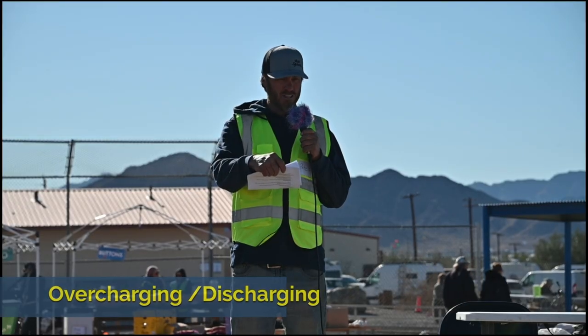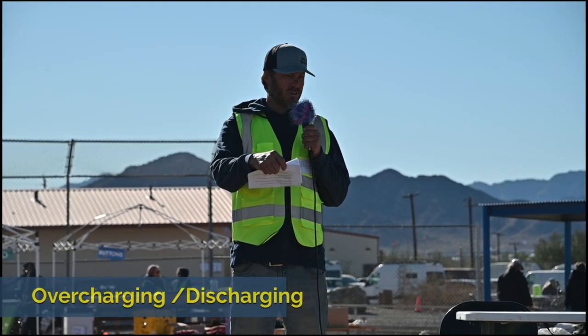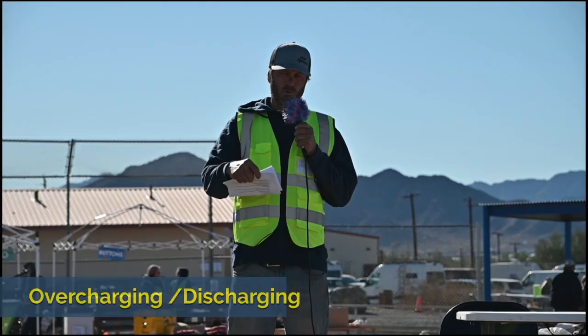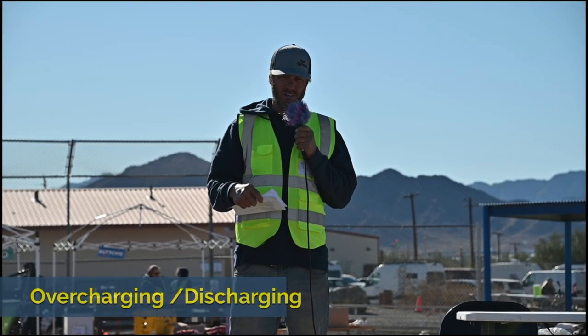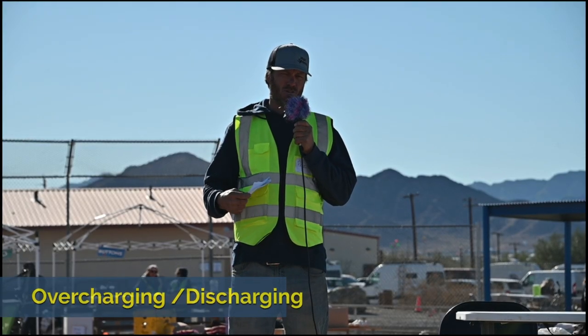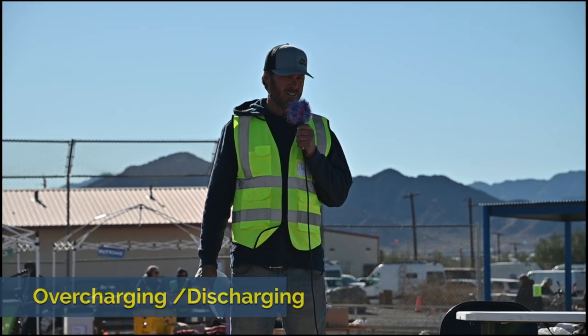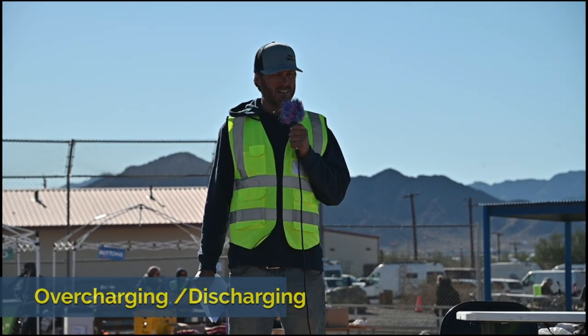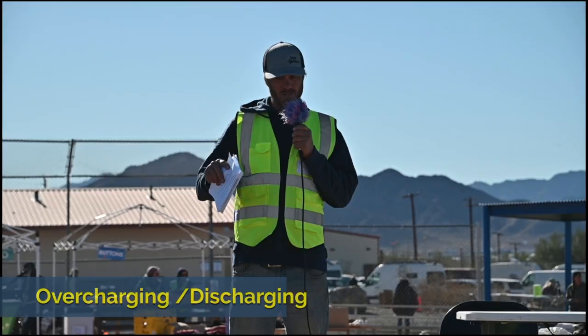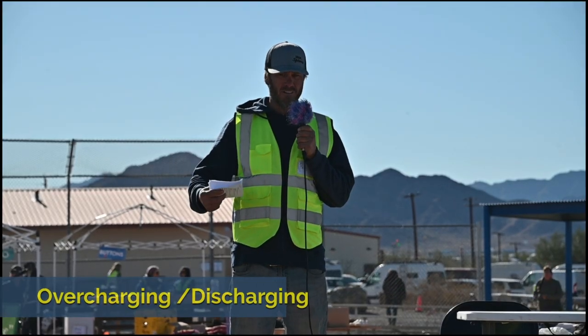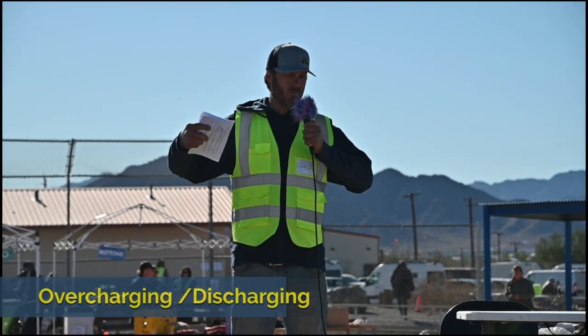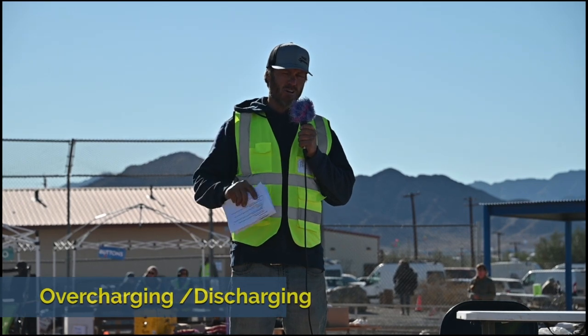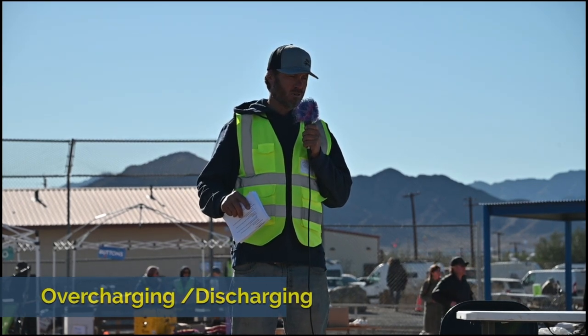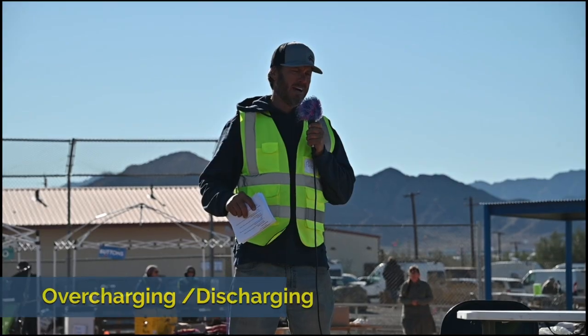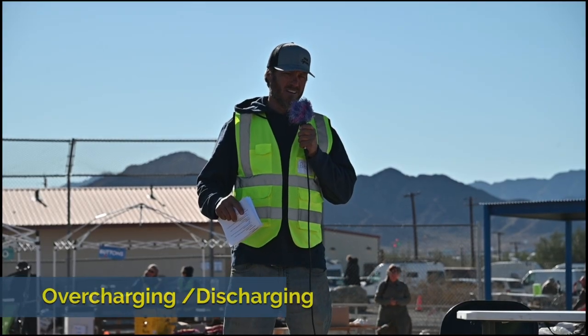Overcharging, deep discharging batteries. If you're noticing that you're having to put water in your batteries at least once a week, that tells me that you're using the crap out of those batteries and you're charging them up the next day at high power because you're boiling the battery. You're literally boiling the water out of that and creating steam. So if you're having to put water in your battery at least once a week, you might want to think about adding a couple more batteries.